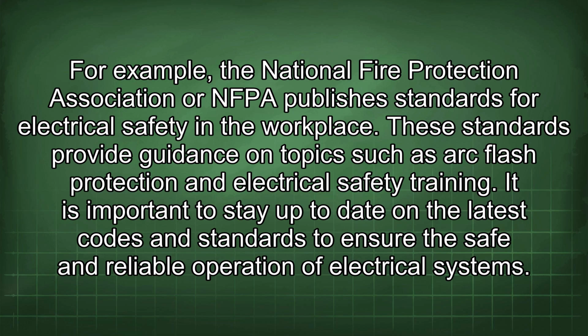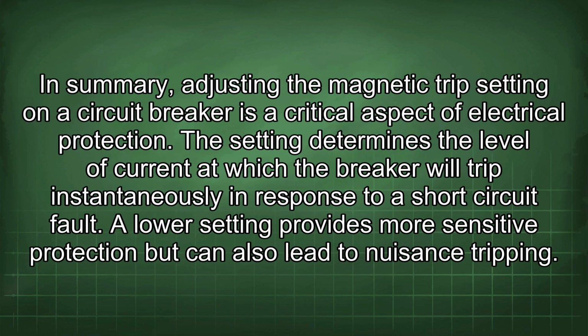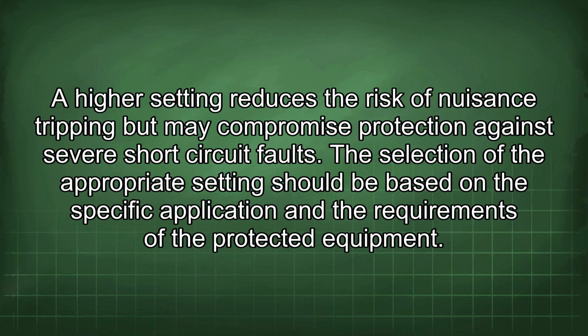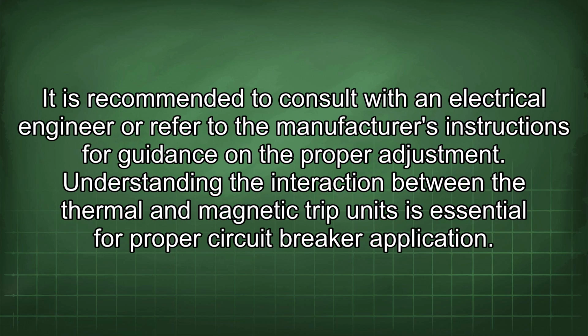In summary, adjusting the magnetic trip setting on a circuit breaker is a critical aspect of electrical protection. The setting determines the level of current at which the breaker will trip instantaneously in response to a short circuit fault. A low setting provides more sensitive protection but can also lead to nuisance tripping. A higher setting reduces the risk of nuisance tripping but may compromise protection against severe short circuit faults. The selection of the appropriate setting should be based on the specific application and the requirements of the protected equipment. It is recommended to consult with an electrical engineer or refer to the manufacturer's instructions for guidance on the proper adjustment.